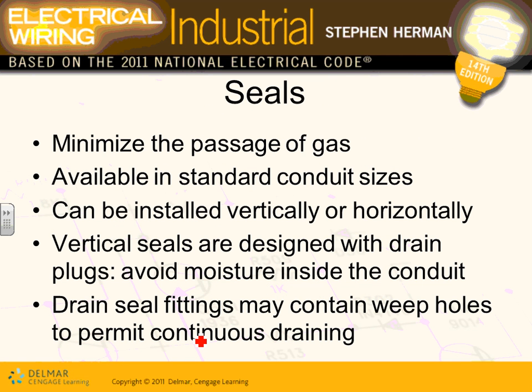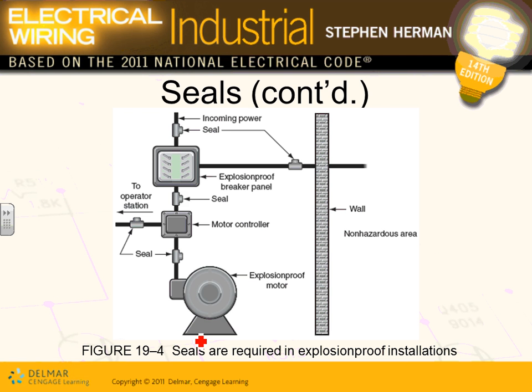Okay, seals. What they do, guys, is they seal around the electrical equipment so the gas does not seep in. Look what they do. So here's my non-hazardous location. This is a gas, natural gas in this area. Look at the explosion proof. Can you guys see the explosion proof equipment that you have right here? This is a panel. They have an explosion proof breaker panel. There's an explosion proof controller. These are rigid conduits. They use rigid conduit. Then they use seals. Can you guys see all these seals? All these seals, what they do is a fitting has an opening in it, and they put a seal. So if the gas is to seep somehow through this conduit, it will stop right here. It wouldn't be able to enter.